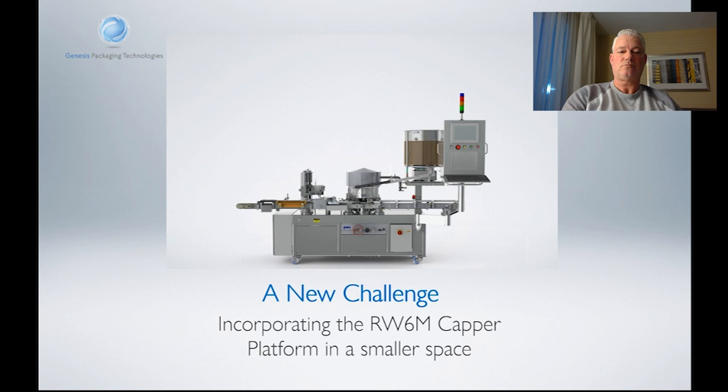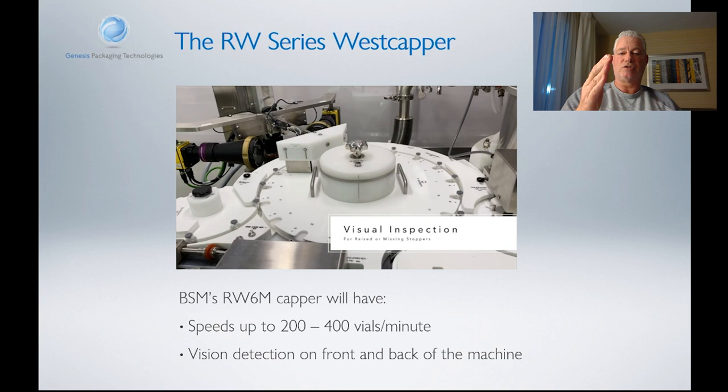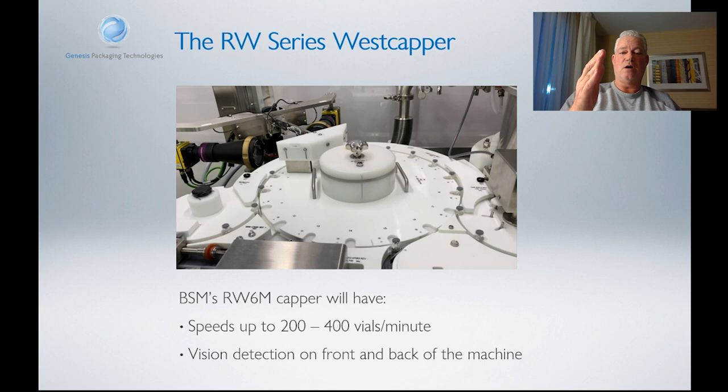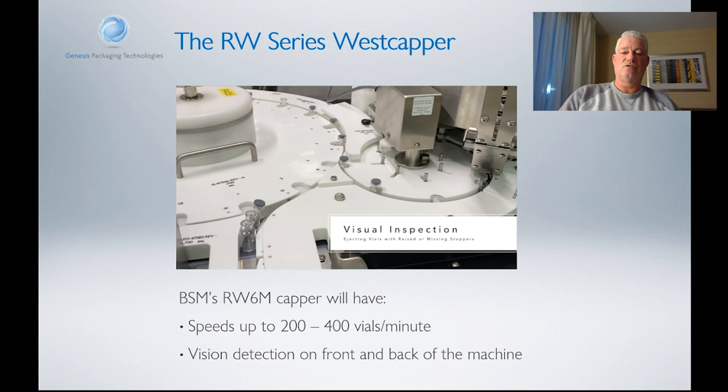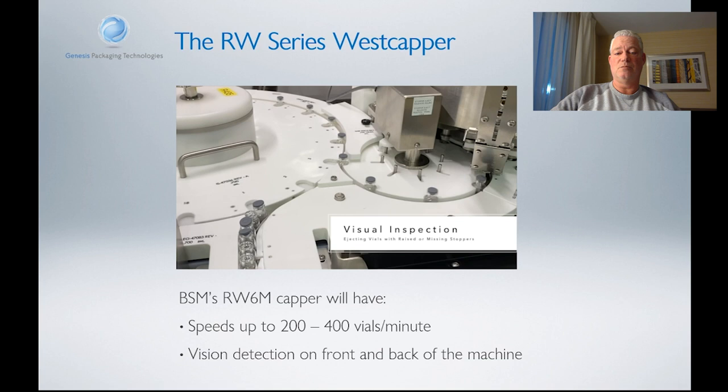We're able to design the RW6M to meet Berkshire's stringent requirements, meet the size, the speed, the output, and the vision detection systems. We've basically taken the big RW600 platform and shrunk it down into a smaller machine that fits better into the Berkshire production model. This machine will incorporate speeds of up to 200 to 400 vials per minute. It will have vision detection systems at the front end for stopper detection as well as the back end for missing cap detection. It is under a RABs, under Grade A quality air with unidirectional flow, and we're working very closely with Steriline to maximize the success of this project.